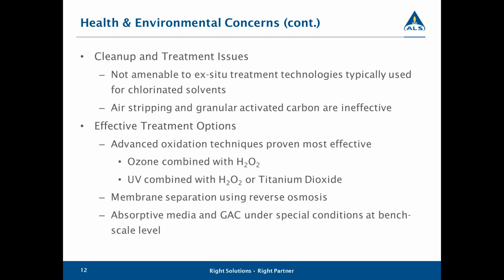The other issue with it is cleanup and treatment. It's not amenable to a lot of normal treatment technologies that are used for chlorinated solvents. Air stripping and activated carbon are ineffective in treating it. There have been a couple of effective treatment options for it, including advanced oxidation techniques. A couple of the ones that have been most effective are ozone combined with hydrogen peroxide, as well as UV combined with hydrogen peroxide or titanium dioxide.